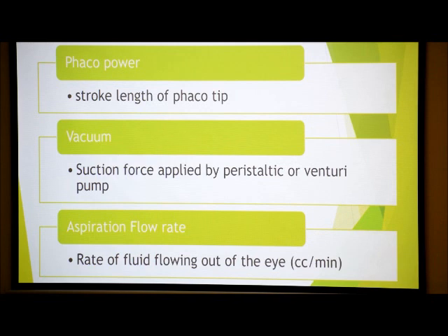Before we go to the understanding of the total mechanics of how the machine works, that is called phaco-dynamics, we should get familiar with a few terminologies. One is phaco power, that is stroke length, the length the phaco tip moves forward and backward; that length is proportionate to the phaco power. Vacuum is the suction force applied by peristaltic or venturi pump at the phaco tip. Aspiration flow rate is the rate at which fluid is drawn out of the eye cavity along with cortex or nuclear fragments. It is measured in ml per minute.